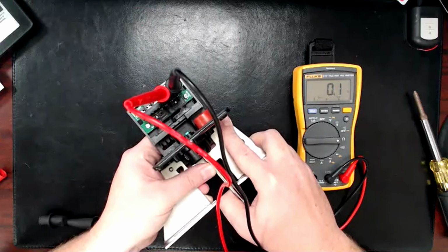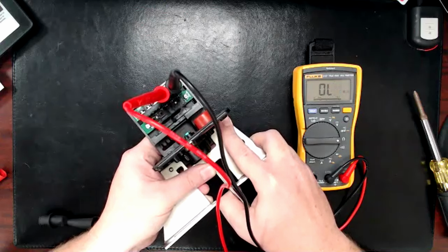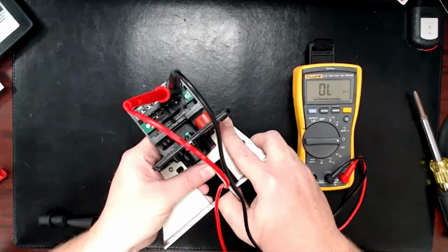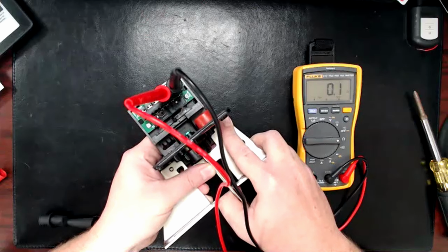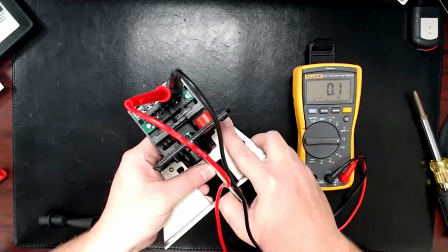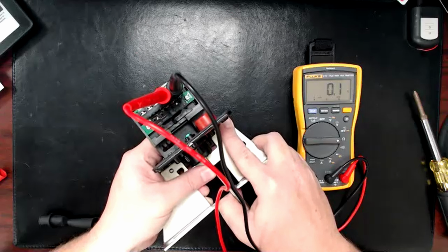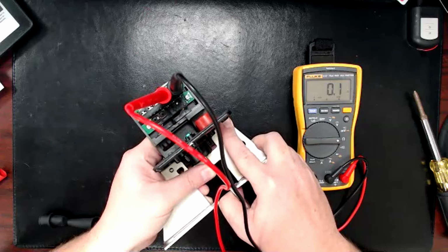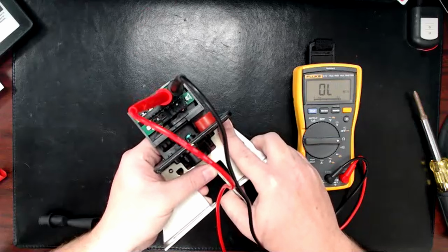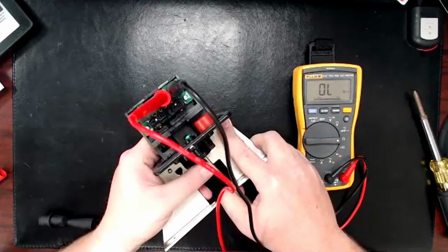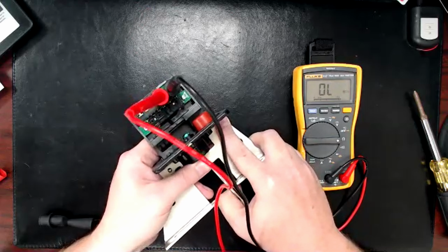The other thing I see is sometimes they'll set it where it's right here on the edge so that everything reads right. Right now you're reading a short because I have it wired backwards. But you turn that valve maybe a quarter turn and then it clicks to that, and then you can keep going all you want. You can close that valve all the way and everything still works right.